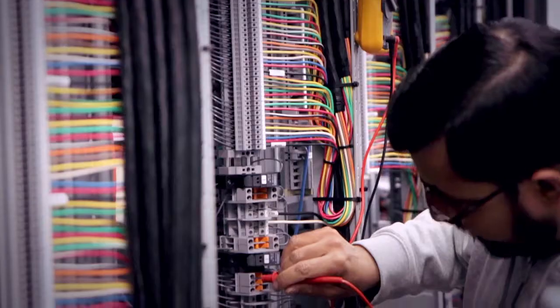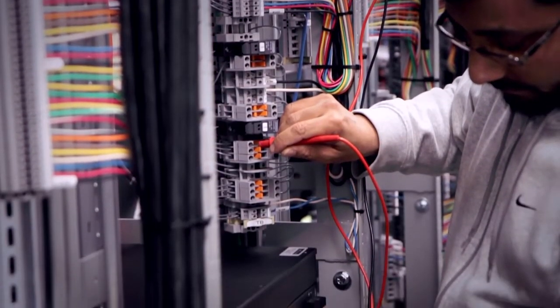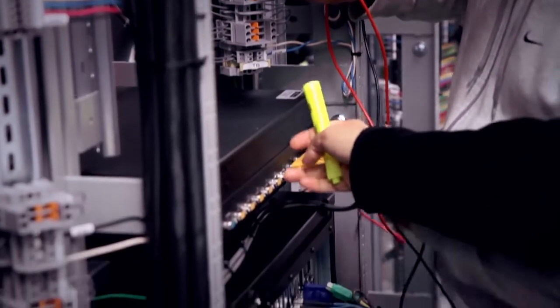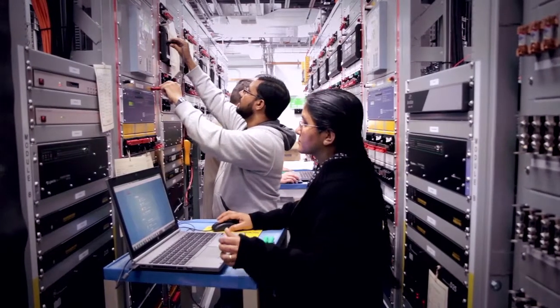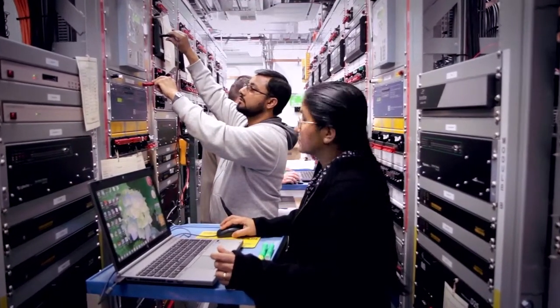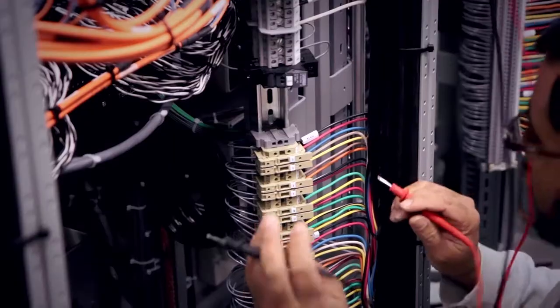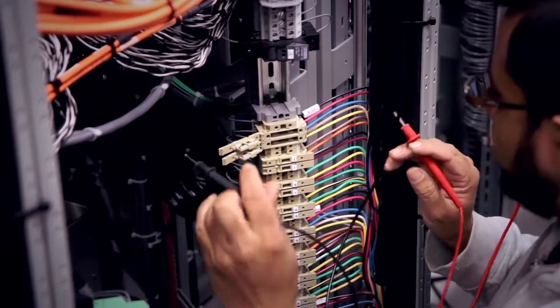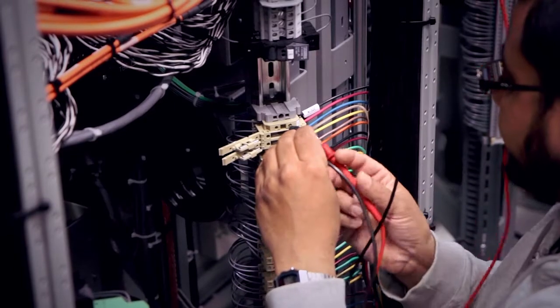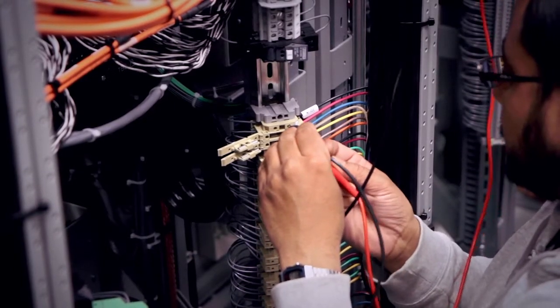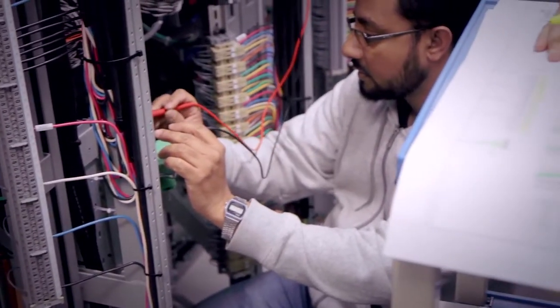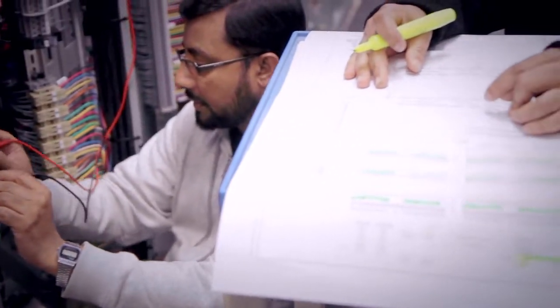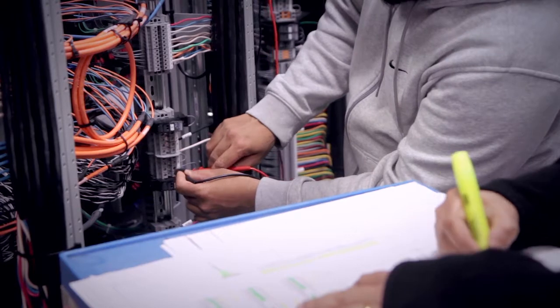Testing is a critical step in quality control, and so Virelec's quality management system includes detailed procedures and working instructions for carrying out the required tests. The schematic and cabling drawings are once again the tester's standard. In a typical control house, every single interconnection is point-to-point tested, and the corresponding connection on the drawings is highlighted in green as being correct. These test drawings are an important quality control record.